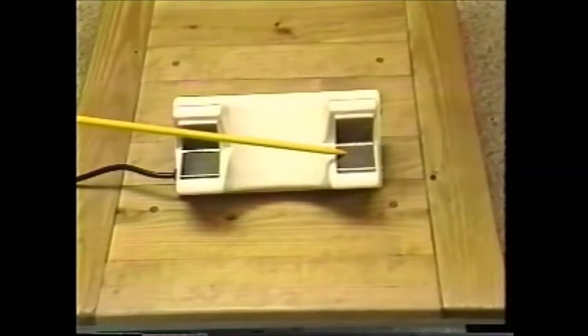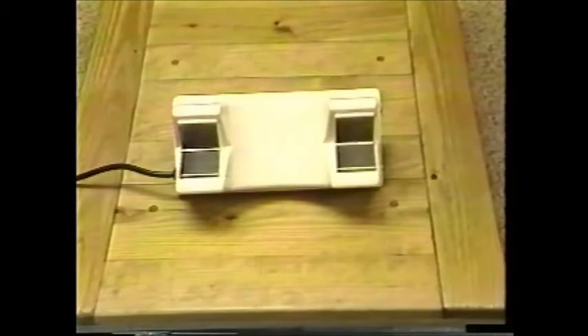In order to provide worker protection, the current supplied to the high voltage electrodes is limited by two resistors. The resistors are in series with the high voltage transformer leads. Either resistor is capable of withstanding the full voltage and limit the current to a safe level if necessary. Additionally, the amplifier monitors the total current flowing through the circuit and will disconnect the high voltage source should the total current exceed normal test levels.